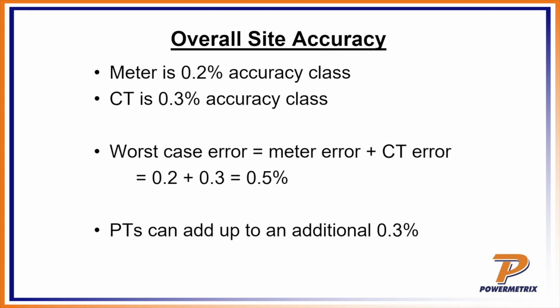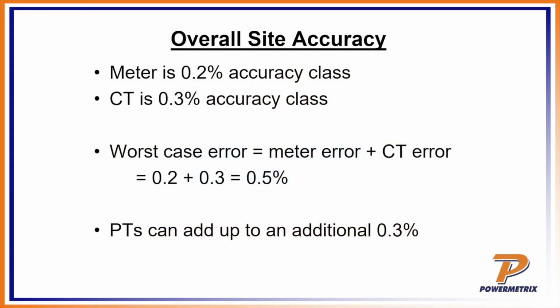We're talking about all of these different things: you've got the wire, you've got the CTs, you've got the PTs. What you can look at, and you're going to have to when you're designing these sites, is the overall site accuracy, because you've got all the accuracy. I've got the accuracy of this component, I've got the accuracy of this component, and I've got the wire between those components that's adding. So I've got to consider all of these things when I'm doing this. So if the meter is 0.2% accuracy class and the CT is 0.3, in this case, worst case scenario, you've got 0.2 plus 0.3, so you're at 0.5 when you add those in. Remember, if you add the PTs in, you're going to add another 0.3 into it, okay?